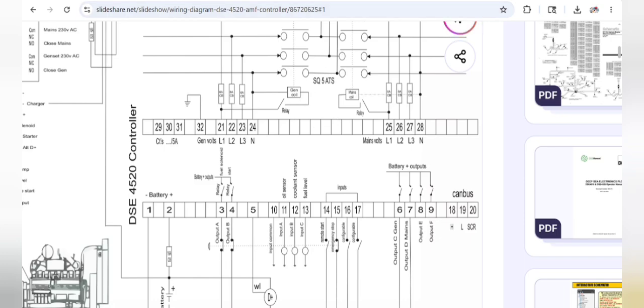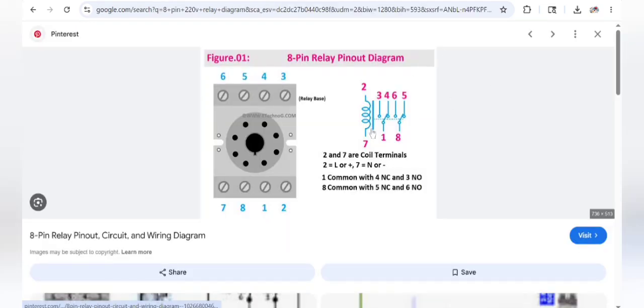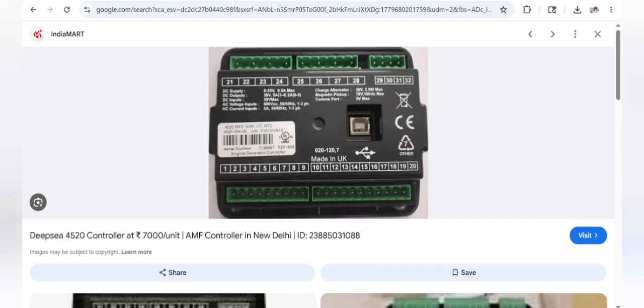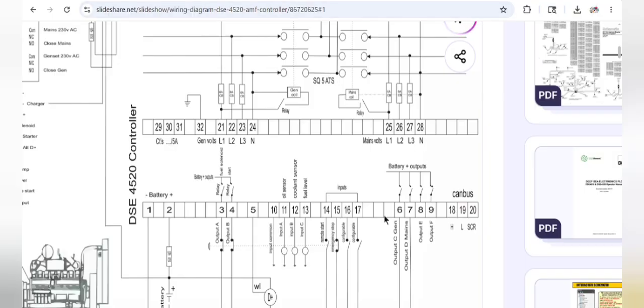Understand? Again, when the main power comes back, this relay will be energized and will break the contact you are using for the ground signal feeding to pin 14. The ground feeding will be disconnected from pin 14, and the controller, sensing no ground signal since the main power is back, will stop the generator. So this is the complete detail about the auto mains failure installation methods.